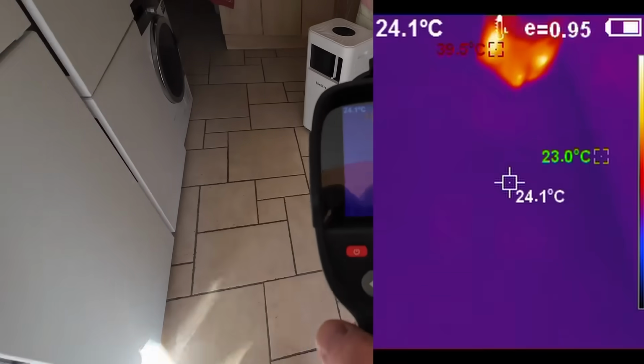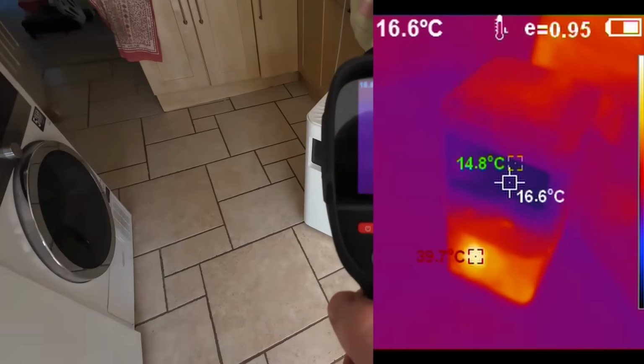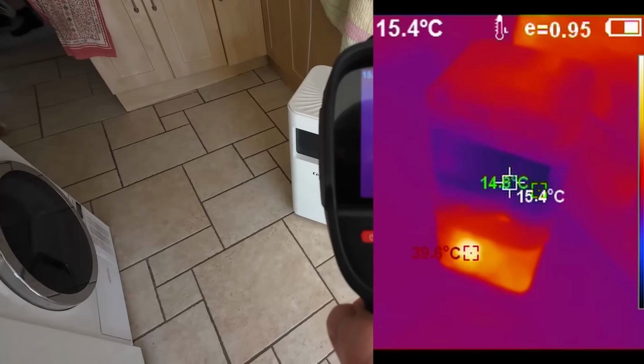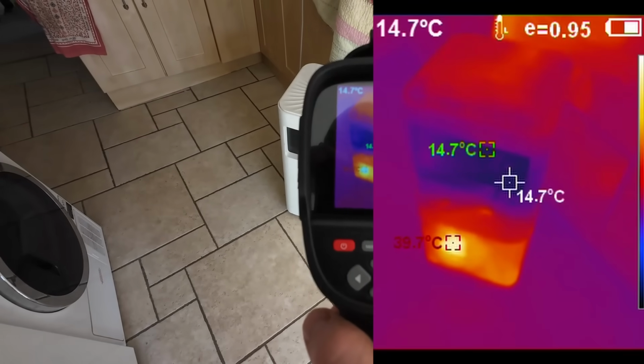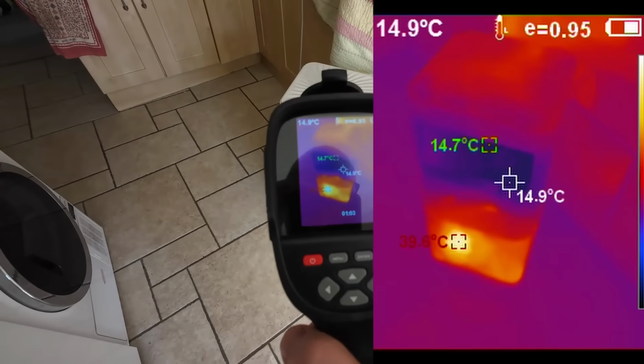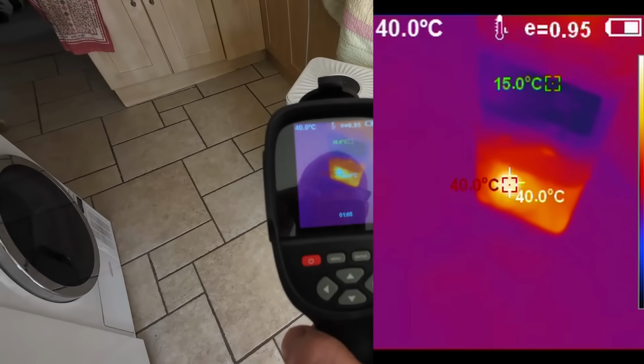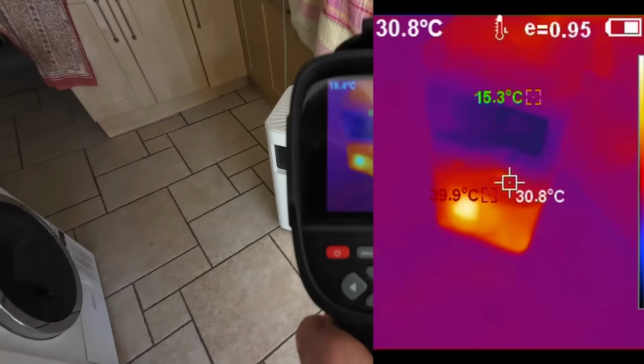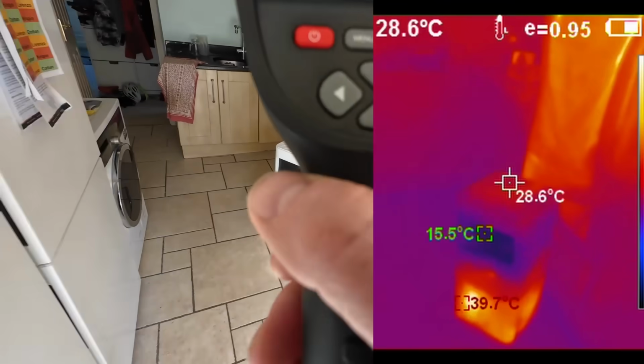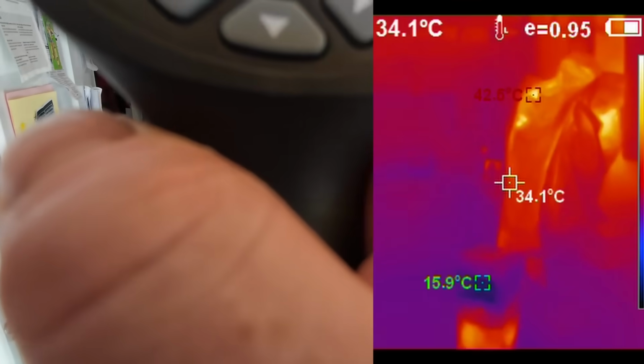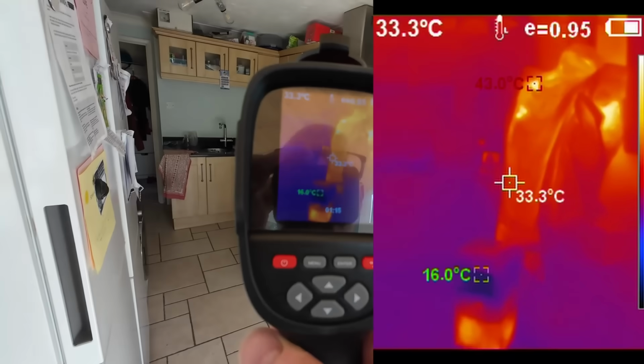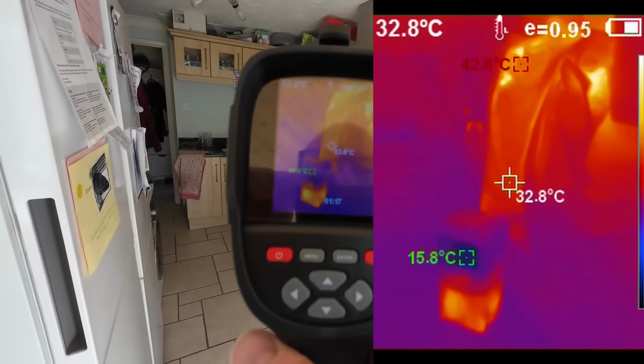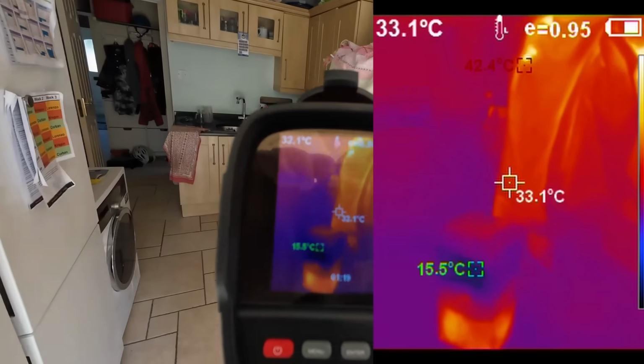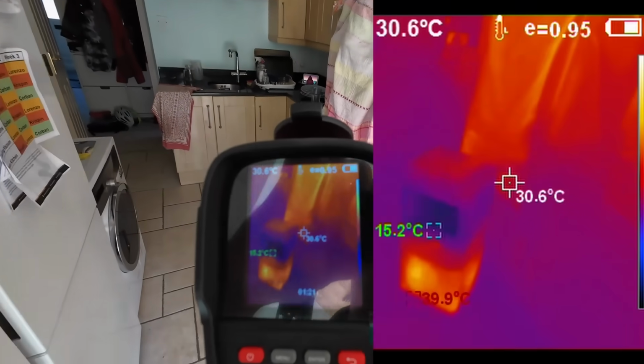But what I wanted to show you was the outlet temperature, 14.6, 14.7 degrees. You can see obviously where the compressor's down there working hard, 40 degrees. And if I take it back, you can see the bigger picture. You can see where it's nice and hot, oh I'm doing a terrible job with this, and you can see where it's very cold. That's your little thermal imaging camera check.